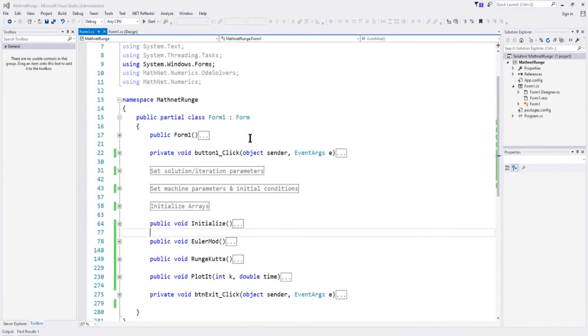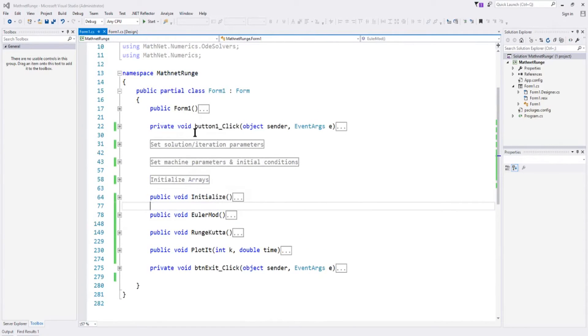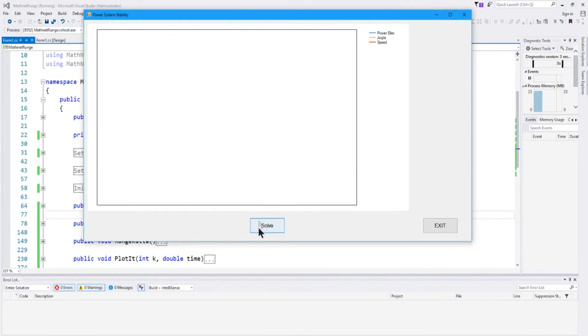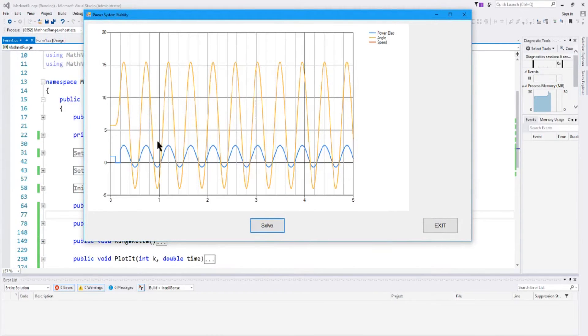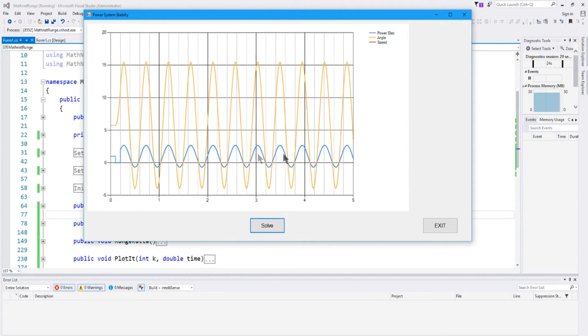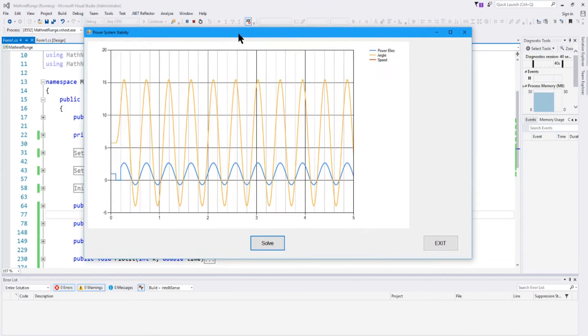Here is the application we're writing. A lot of this is very similar to the previous video where we did the modified Euler. We've got a chart and two buttons — we click Solve, and it takes our simple classical model, starts at T equals 0.1 to apply the three-phase fault where power goes to zero, then clears the fault at T equals 0.2. You can see the electrical power oscillates as the machine recovers from that disturbance, and the angle oscillates proportionally — starting at about six degrees, going up to about 15 degrees and oscillating back and forth. This matches very well what we did with our industry standard power system simulator.